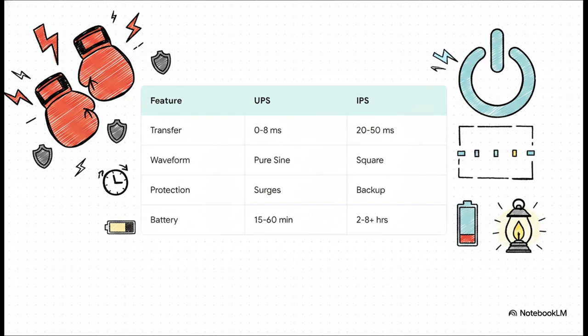Over in the IPS corner, you have slower but incredibly long-lasting raw power. The transfer time is a noticeable 20 to 50 milliseconds, and it primarily just provides backup power without all that heavy filtering. But look at that battery life. It can keep the lights on for 2 to 8 hours, or even more.